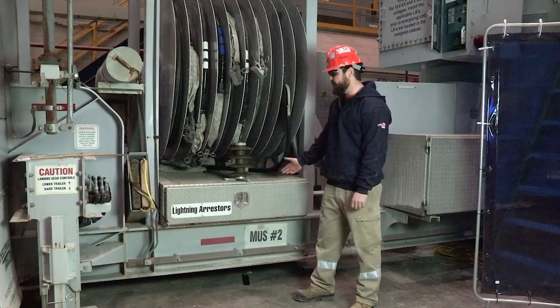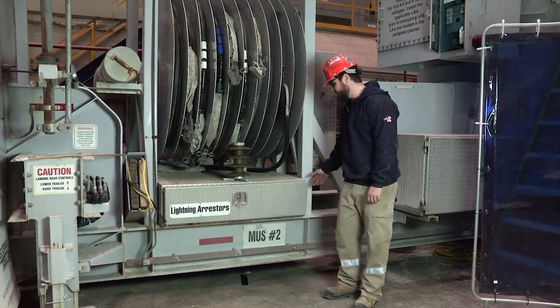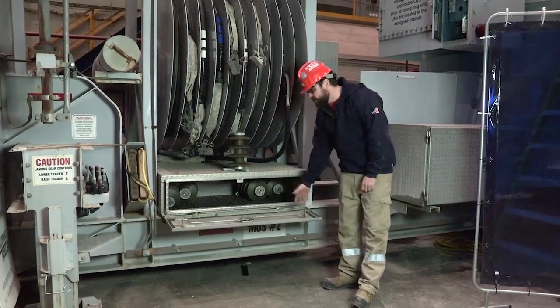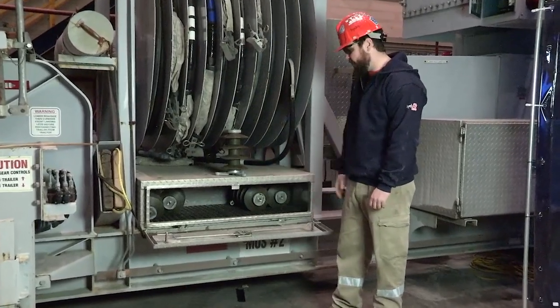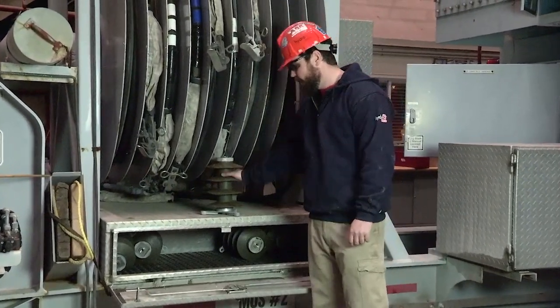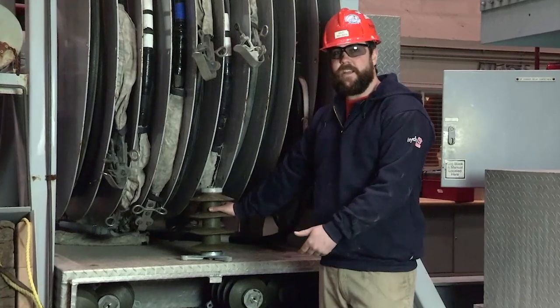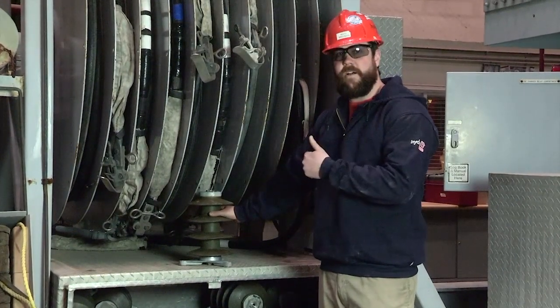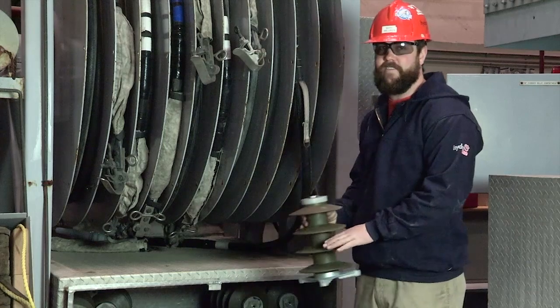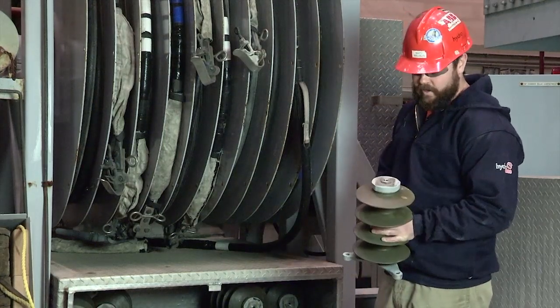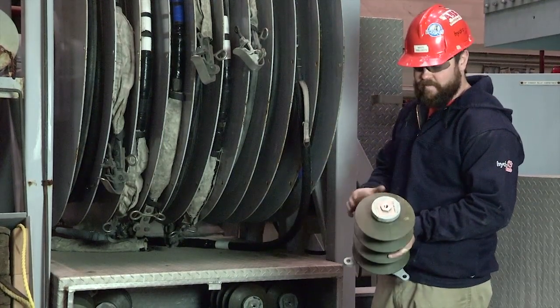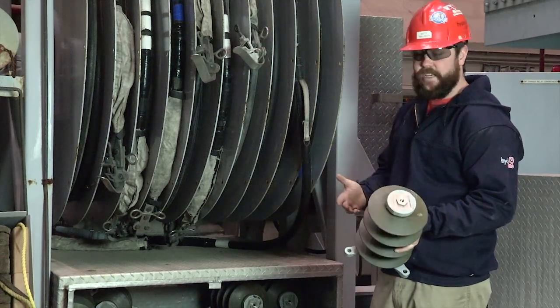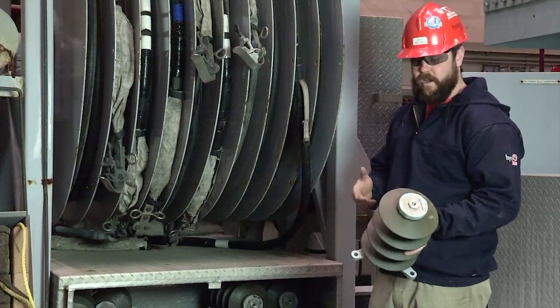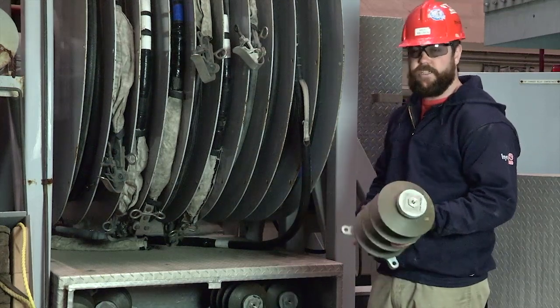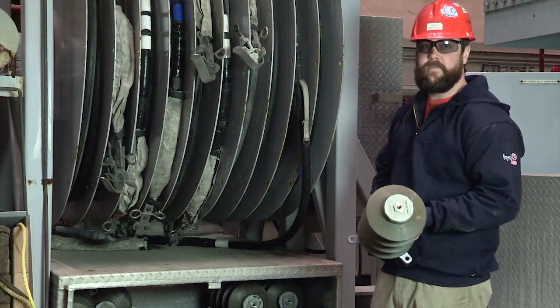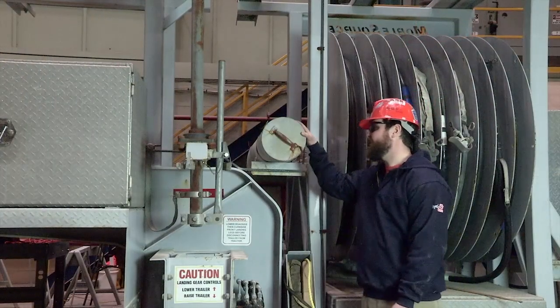All right, up next we have the lightning arrestor bin. Same thing as all the other bins we've been looking at, just make sure that they've got good seals and grease. Obviously that one's a little squeaky. What you want to do is just make sure that this is carrying the right LAs for the voltages that are on the MUS. So multiple voltages, you're going to have multiple LAs. And what you're going to be looking at is the MCOV rating, which you can find in your manufacturer manual for what LAs you need, or if not, you can contact MTS and they'll guide you to the right LA you need.